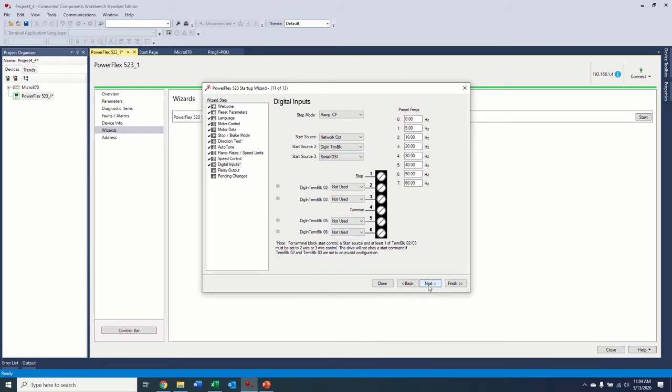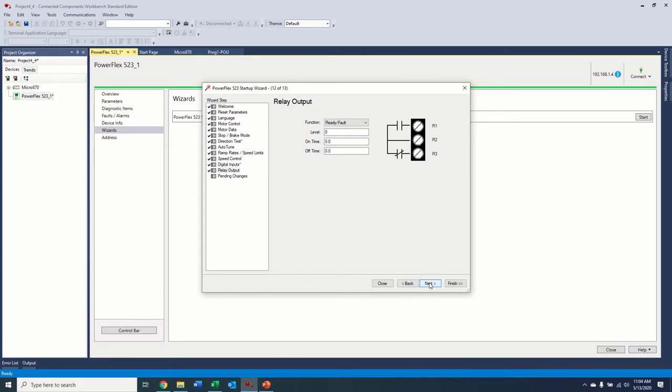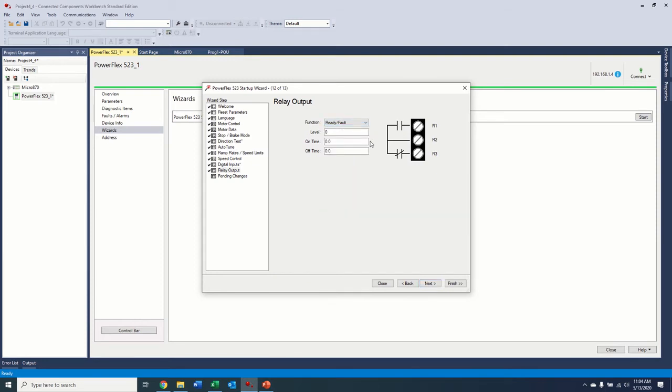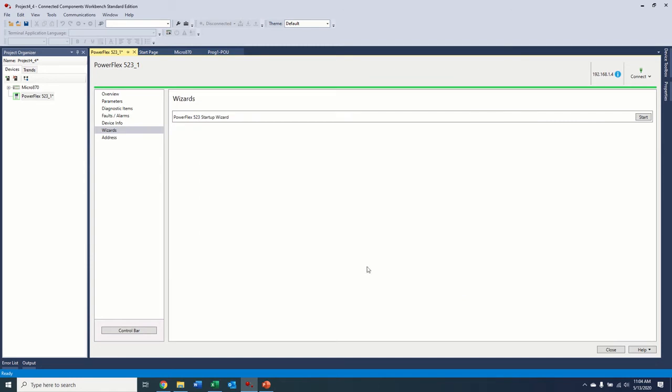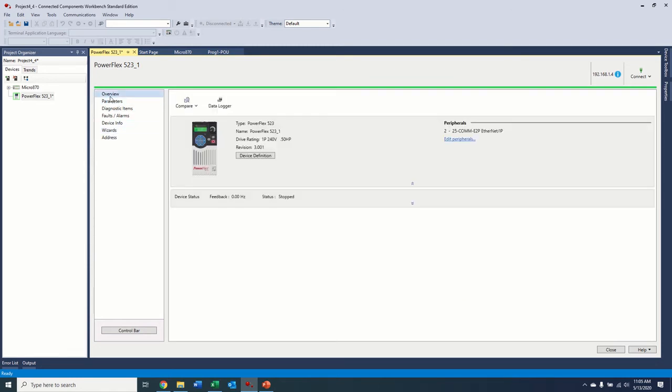And then our output, relay output, we're not using that. So we can just leave that as default. And then we get to the end, and it'll tell us what our pending changes are. What did we do? So it tells us that these parameters are going to be changed when we click finish. And there we go. So we're ready to go. We're ready to start our drive over the network. So the next step will be putting the programming into the controller to control the drive.